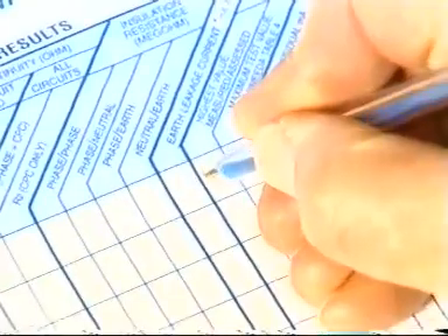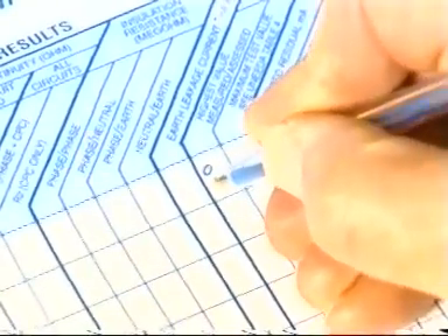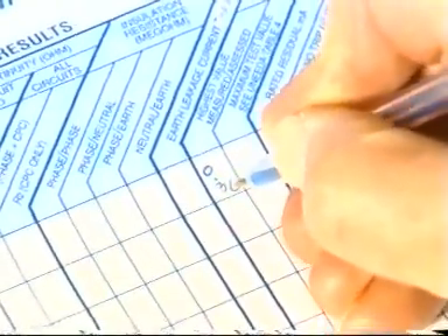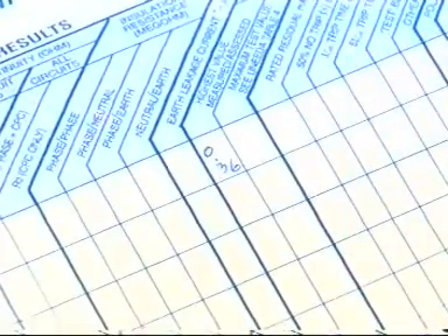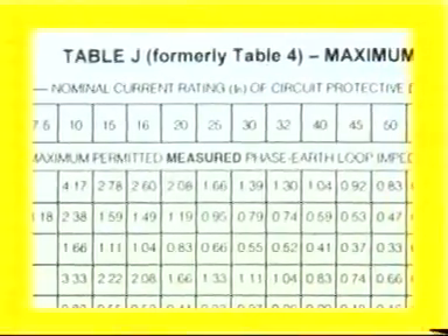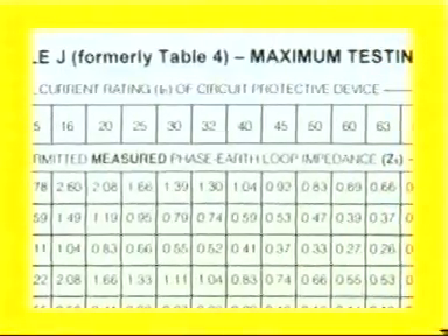The recorded impedance can be adjusted to take account of ambient temperature and cable characteristics and compared directly with design values from BS7671. To avoid calculations, the measured value as appearing on the loop tester may be compared directly with pre-calculated values such as shown in Table J of the Practical Guide to Electrical Installation Testing.